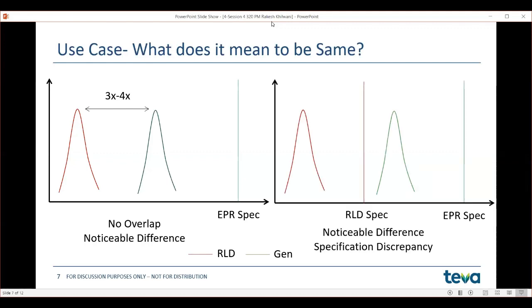And the last one is even more drastic. What if there's a noticeable difference, but there's a discrepancy in the specification? Again, we do not know what the RLD spec was. And again, there's a difference in methodology. Whatever the innovator did, or the RLD manufacturer is doing, might use different test conditions, and they have set their specification based on those conditions. It might not match mine. So probably there is room to say that we should not look at the RLD spec in a vacuum. But again, a reviewer looking at it might not have the same opinion, and it might lead to a negative response or a deficiency request from the agency. So these are some of the scenarios that we would encounter when we're comparing or showing how the RLD behaves with respect to the generic product.